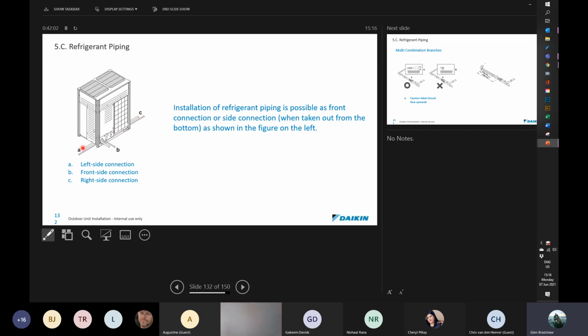So quite a nice way of doing it is to do the piping underneath the unit. This protects the piping from people standing on it. I find that when the piping is in front of the unit, very often you'll see after a while it's bent back because every technician who has to get inside the electrical panel has to stand on top of the piping. And this just causes a problem. And it can also cause the ref nets on multi-systems to crack. Okay, so basically that's the 3 configurations. And the one that I really would recommend is that the guys use going underneath the unit, okay, rather than coming in through the front.